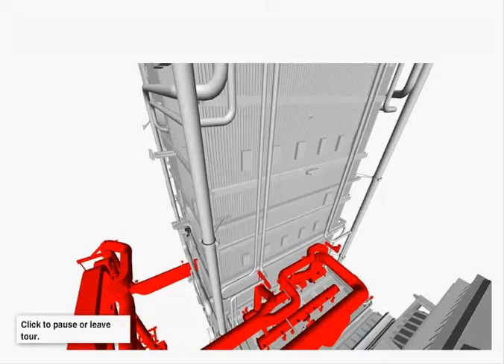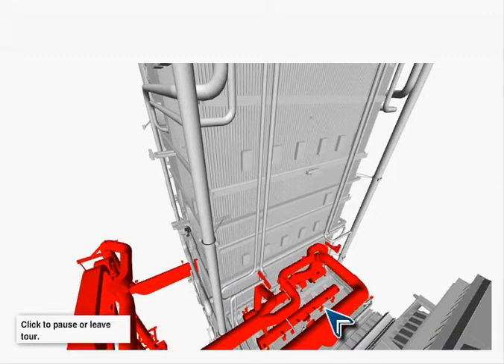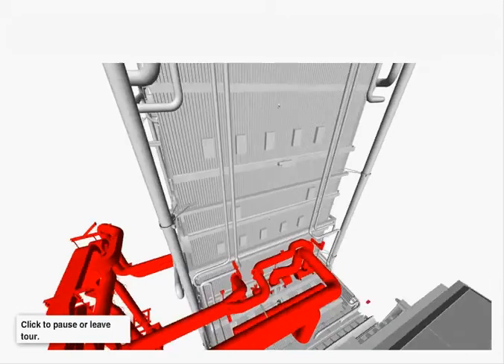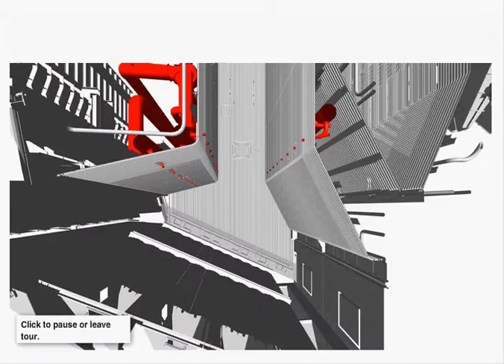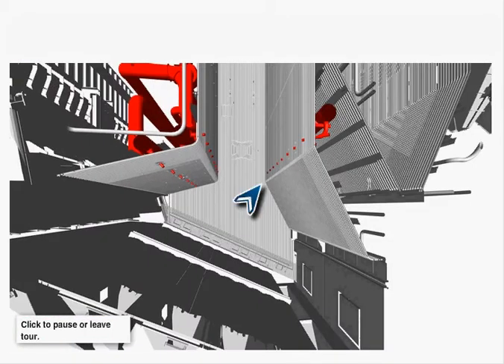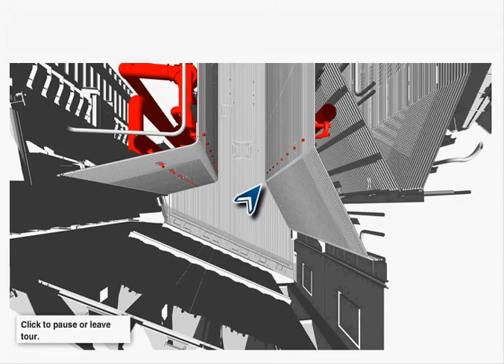Our secondary air consists of two subsystems. The secondary air nozzles, which are in the ceiling of the furnace, are used to enhance the combustion process and stabilize the ignition zone of the waste that enters the furnace. This gives a better combustion and burnout. The other part of the secondary air is located in the inlet to the first boiler pass. The system is designed with our CFD tool under the trademark Volumix.